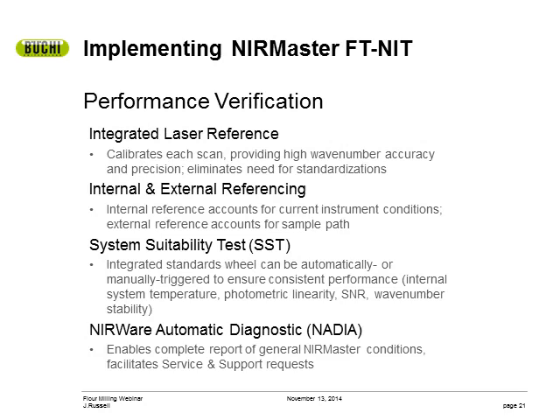There are also a lot of features within the Buchi NIRMaster for performance verification. There is an integrated laser reference, and we have internal and external referencing that will help accommodate for current instrument conditions and different path lengths. We have a system suitability test that is run typically every 24 hours, and that test will tell you every single day that your NIRMaster is performing perfectly. In addition, we have a more comprehensive diagnostic test called the NADIA, which can let the service engineers know exactly what is going on with your unit.